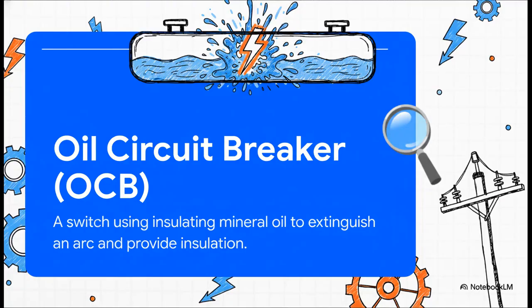And that's how we got the oil circuit breaker, or OCB for short. This device uses a whole bath of mineral oil, not just to insulate things. Nope, that oil is its main weapon—what it uses to physically extinguish the electrical arc during a huge fault.